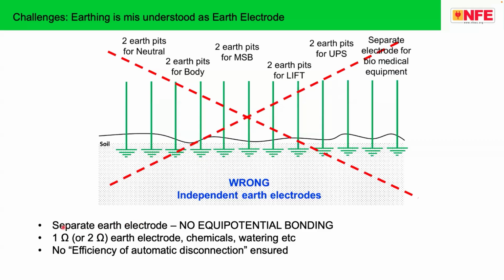The challenge which we see in most of the hospitals is that there are hundreds of earth electrodes, 50 to 100 earth electrodes, and there is no equipotential bonding, which is a violation of the fundamental electrical safety measure. The biomedical equipment manufacturers are always demanding a 1 ohm or 2 ohm earth electrode. And then they say you use chemicals or you put water into the earth electrode in order to achieve this resistance, which is absolutely wrong. This is a big mistake. And no efficient automatic disconnection is ensured.